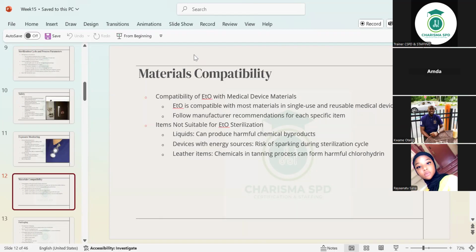ETO is a very good one when it comes to materials. It's compatible with most materials in single-use and reusable medical devices. It's very compatible with them, but you have to follow the manufacturer's recommendations for each specific item. It's good for a lot of them, but your choice should follow the manufacturer's recommendations.